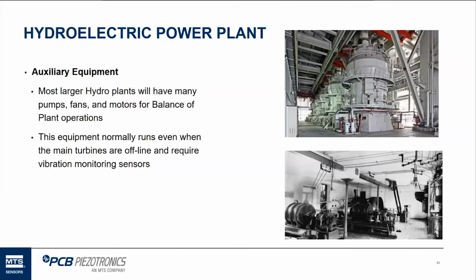Another note on auxiliary equipment: it typically always runs, even when the main turbines are not, because it's supplying maybe fans or keeping some sort of flow running within the hydro unit as well. So it's usually always running. I've seen some redundancy as well in some hydro plants, with redundant auxiliary equipment in case there's a failure.